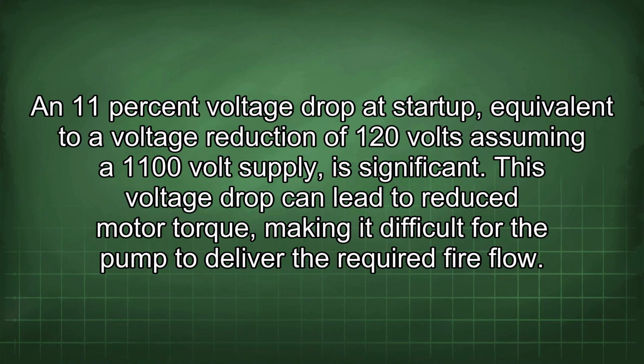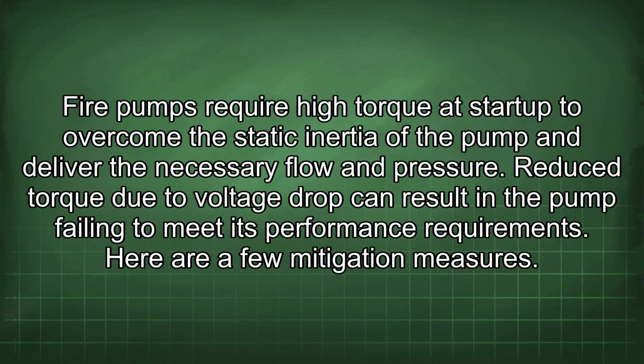An 11% voltage drop at startup, equivalent to a voltage reduction of 120 volts assuming a 1100 volt supply, is significant. This voltage drop can lead to reduced motor torque, making it difficult for the pump to deliver the required fire flow. Fire pumps require high torque at startup to overcome the static inertia of the pump and deliver the necessary flow and pressure. Reduced torque due to voltage drop can result in the pump failing to meet its performance requirements. Here are a few mitigation measures.